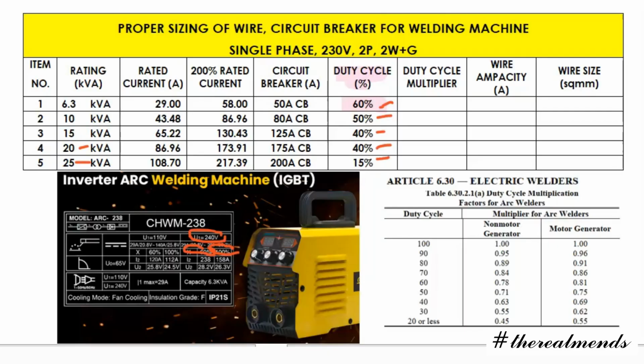So after that, once we have the duty cycle, we can have this duty cycle multiplier. Refer to the PEC, Article 6.30 for electric welders: duty cycle multiplication factors for arc welders. If your duty cycle is 60%, we have 60% here. And then assume that our welding machine is a motor generator. Actually, there is also a value for non-motor. So for now, let's assume our welding machine is a motor generator. For 60%, your multiplier is 0.81. For 50%, your multiplier is 0.75. For 40%, your multiplier is 0.69.